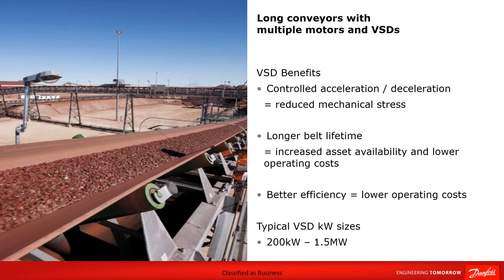What are the benefits? Well, we've mentioned before, controlled acceleration and deceleration, which reduces the mechanical stress. This gives you a longer belt lifetime. So what does that mean? It means you increase your asset availability and you have lower operating costs. You also have better efficiency, which gives you lower operating costs, because the drive will detect the loading on the conveyor. During the course of the day you may not want to run at full speed throughout, so basically 100% all of the time. You may be able to run it at 50% during off-peak times. So your drive will help reduce your energy costs.